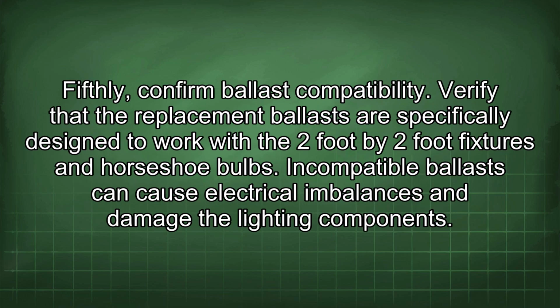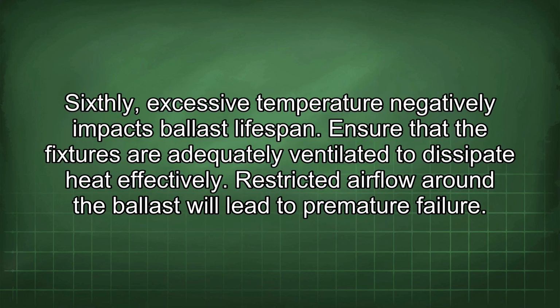Fifthly, confirm ballast compatibility. Verify that the replacement ballasts are specifically designed to work with the 2-foot by 2-foot fixtures and horseshoe bulbs. Incompatible ballasts can cause electrical imbalances and damage the lighting component. Sixthly, excessive temperature negatively impacts ballast lifespan. Ensure that the fixtures are adequately ventilated to dissipate heat effectively. Restricted airflow around the ballast will lead to premature failure.